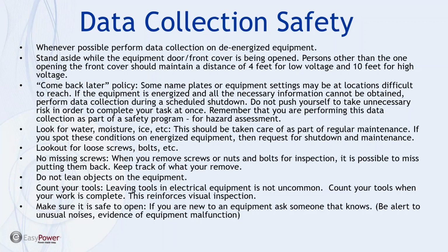Try to limit as much as possible the risks that you have to take, because frequently people trying to remove covers, if they're not used to doing that procedure, can lose their hold on a piece of heavy cover, and it could actually fall into the electrified equipment, causing an arc flash just as a result. So again, safety first during this process, and at the same time, you should look for signs of irregular operations, whether it's moisture forming or loose bolts and screws. And for sure, as you're doing the work, make sure you do not leave tools inside the equipment, and that loose terminals or nuts and bolts that you loosened are accounted for when you put things back together.